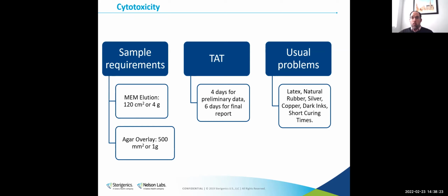We do see normal problems with cytotox as far as materials go, though, like latex, like I mentioned before. That's also true with natural rubbers. A lot of metals are cytotoxic, like silver, copper, zinc. So they're a source. In fact, cytotox is great to evaluate a color change because colorants usually always have a backbone of a metal. And so cytotox, if it's one of those metals that are cytotoxic, would pick it up. We can also run ICP-MS to look for that metal backbone too.